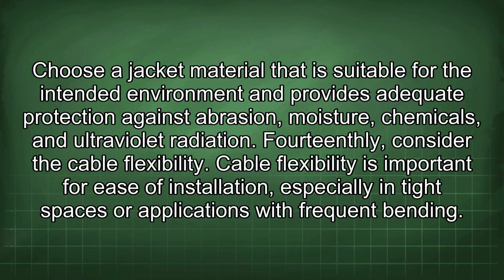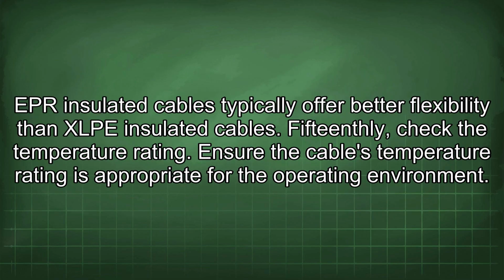Choose a jacket material that is suitable for the intended environment and provides adequate protection against abrasion, moisture, chemicals, and ultraviolet radiation. 14thly, consider the cable flexibility. Cable flexibility is important for ease of installation, especially in tight spaces or applications with frequent bending. EPR insulated cables typically offer better flexibility than XLPE insulated cables.